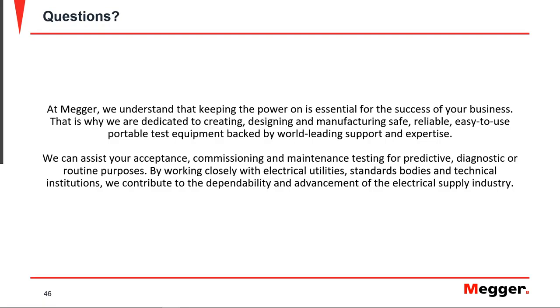All right, thanks. So Daniel, how do you test if the breaker curve is not there in the software? Okay, that's a good question. I meant to explain that during the presentation. I skipped it. So as I mentioned, you do have a large library, but by no means can we claim that we have all breakers, right? So if you have a breaker that is not in the library, the immediate option is to use the generic breaker option in the software. That will allow you to just define a frame size, and also for you as the user to directly type the test currents that you're going to use for that test.